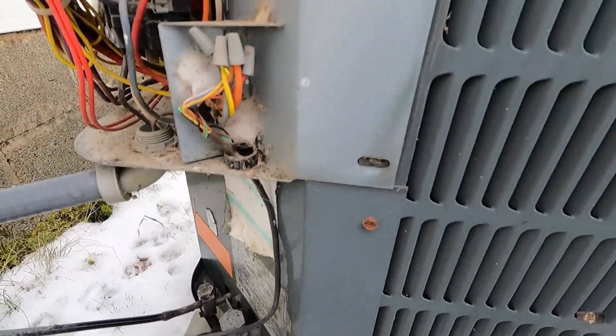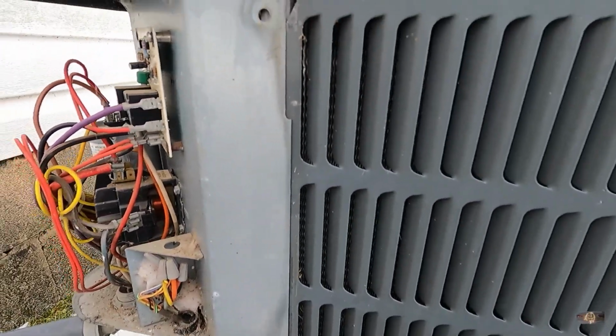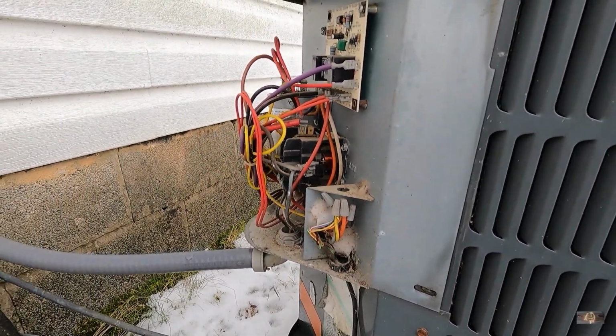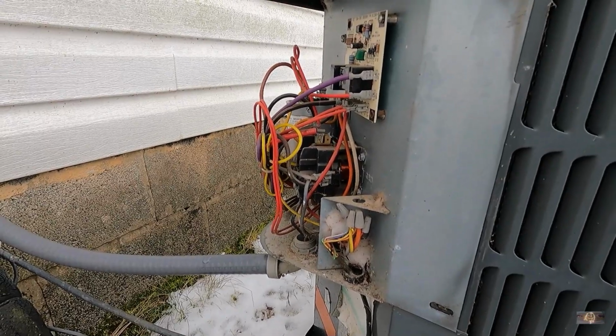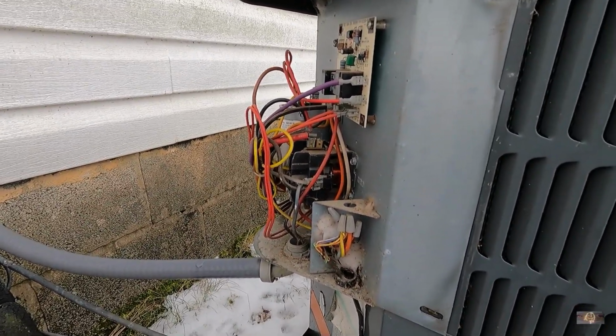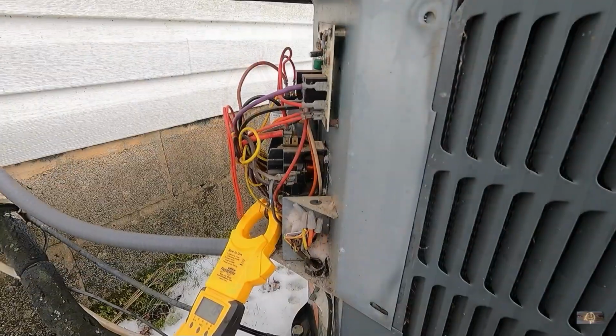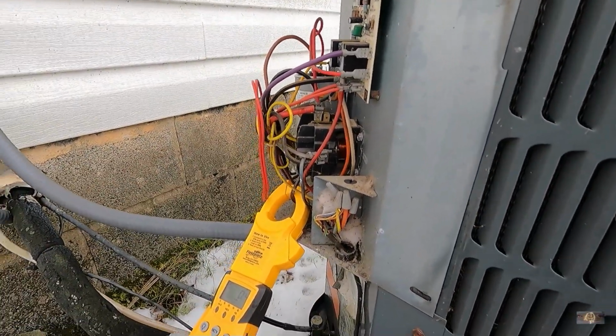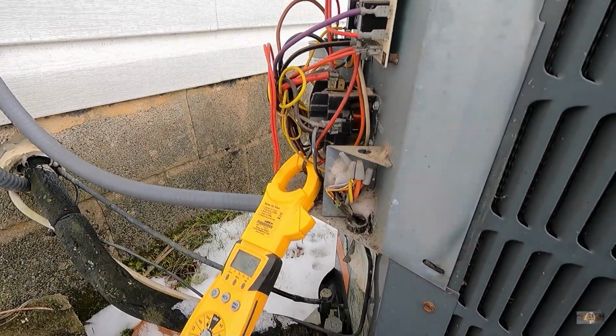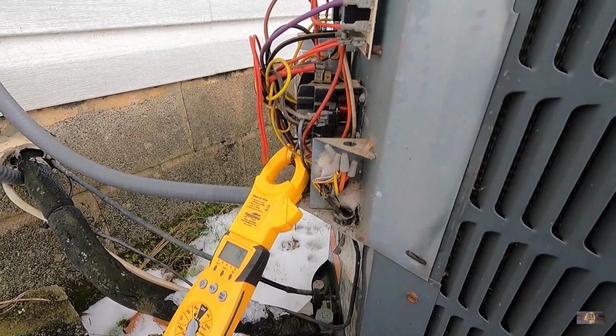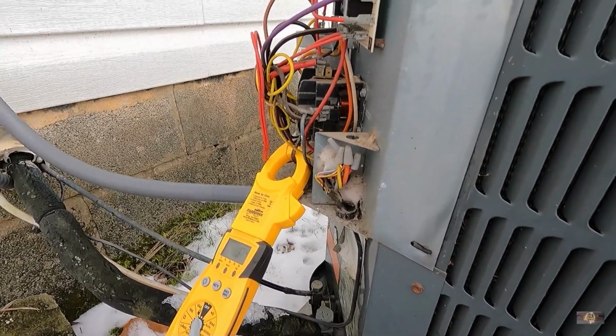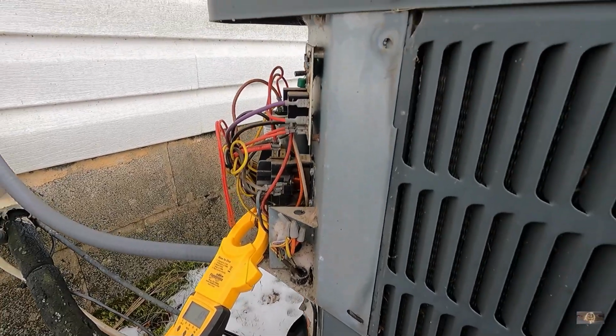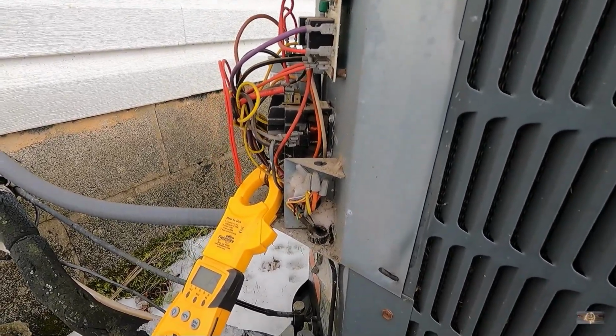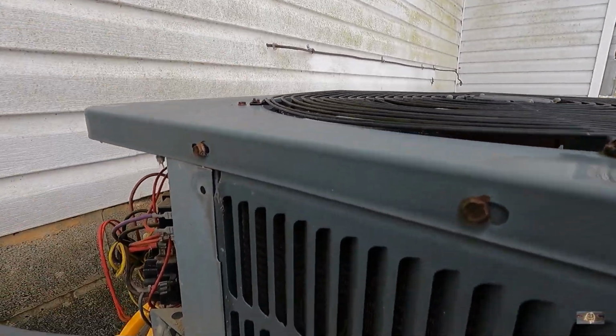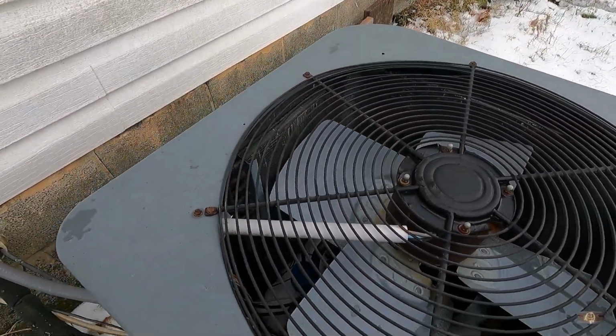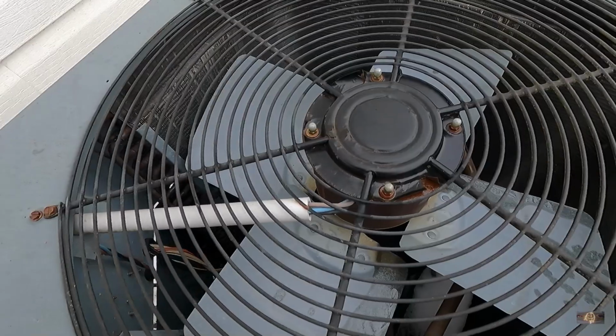It's a shot. So I'm going to go ahead and make sure we got high voltage out here. And I think I'll go ahead and pull the disconnect, just test the capacitor. Just real quick since I'm here. Okay, so the capacitor tested good. I went ahead and put my amp clamp on the power wire coming in. And we're going to do an inrush on it and just see how it does. I'm going to have them fire it up and see if this thing is making noise while it's running. Maybe it was, like I said, ice accumulation. Don't really know. Looks like you got some exposed wires there.